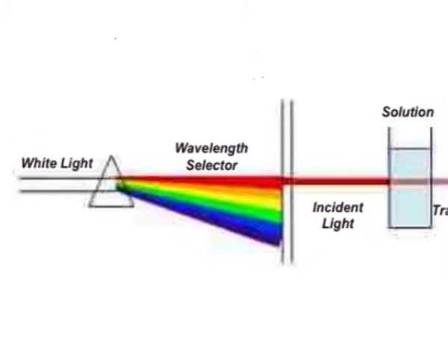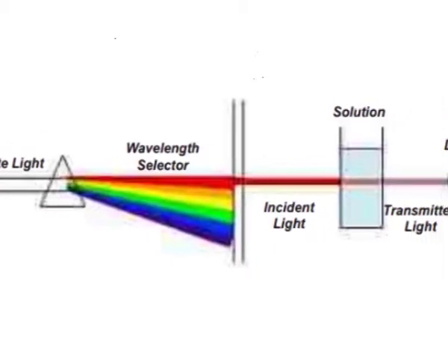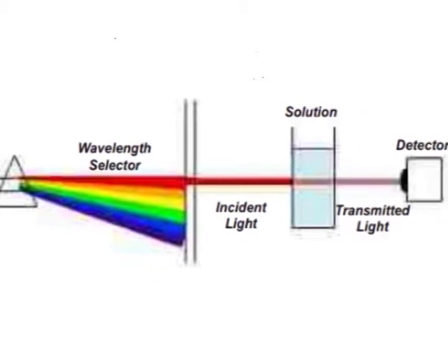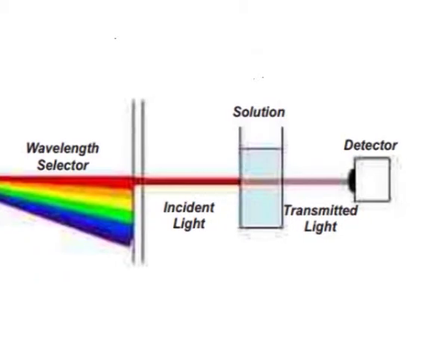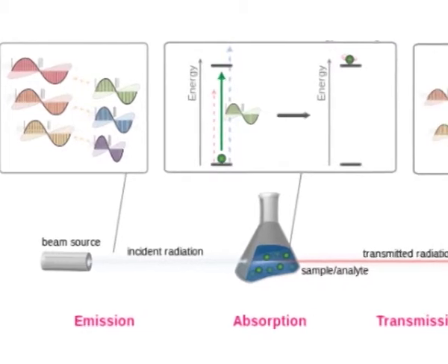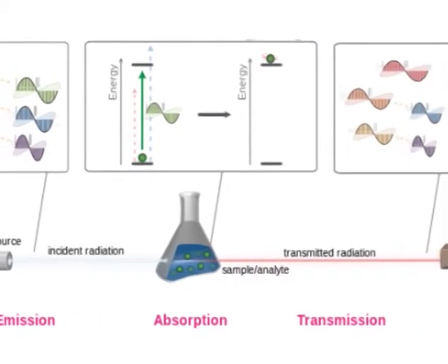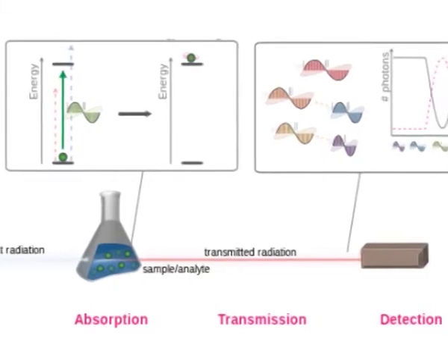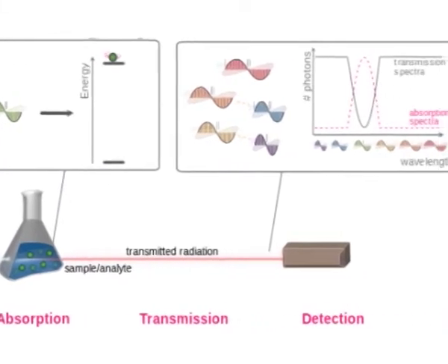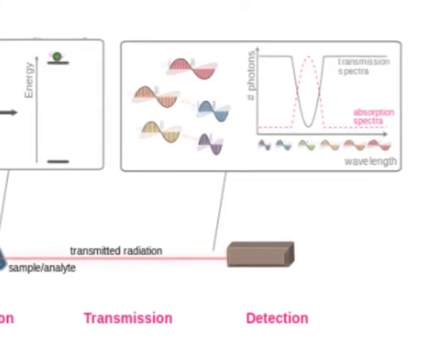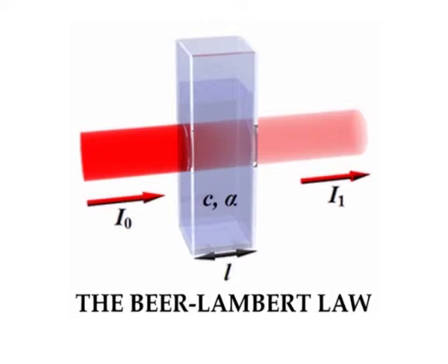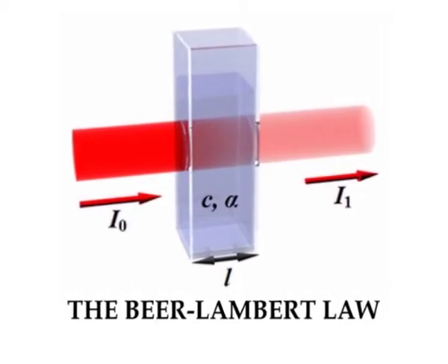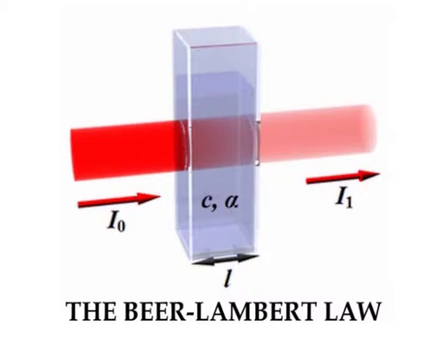A spectrophotometer optically determines the absorbance or transmission of characteristic wavelengths of radiant energy or light by a chemical species in solution. Each molecule absorbs light at certain wavelengths in a unique spectral pattern, because of the number and arrangement of its characteristic functional groups, such as double bonds between carbon atoms. According to the Beer-Lambert law, the amount of light absorbed at these wavelengths is directly proportional to the concentration of the chemical species.